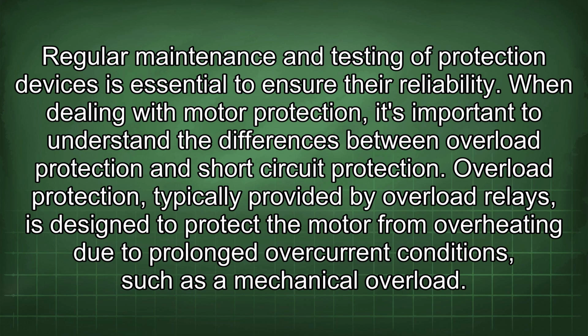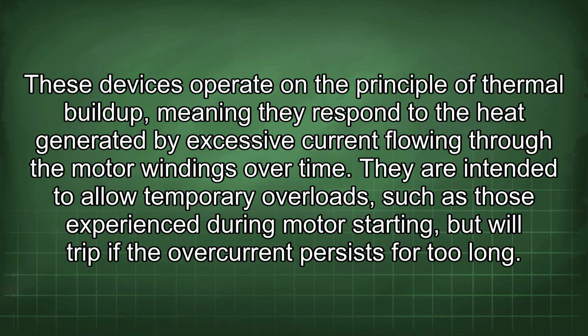Overload protection, typically provided by overload relays, is designed to protect the motor from overheating due to prolonged overcurrent conditions, such as a mechanical overload. These devices operate on the principle of thermal buildup, meaning they respond to the heat generated by excessive current flowing through the motor windings over time. They are intended to allow temporary overloads, such as those experienced during motor starting, but will trip if the overcurrent persists for too long.